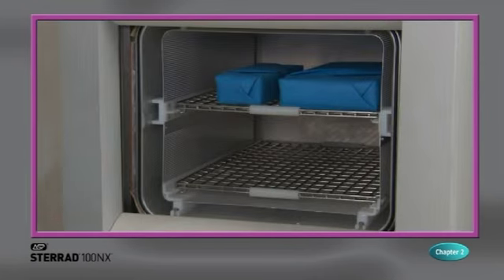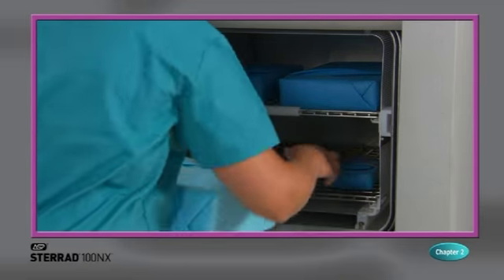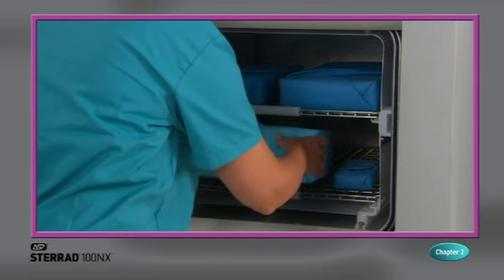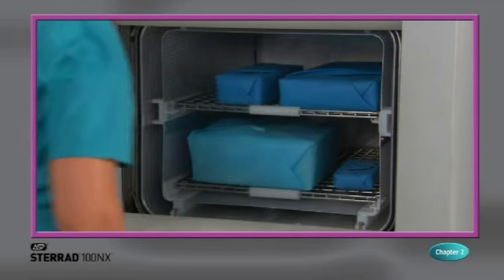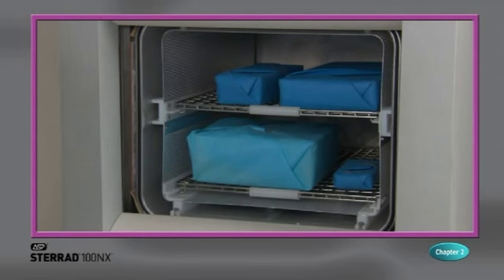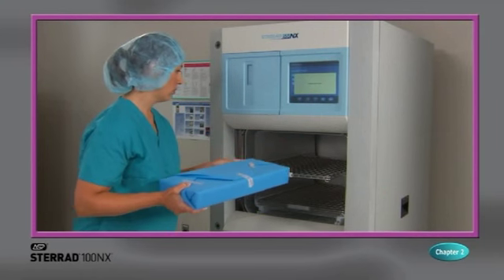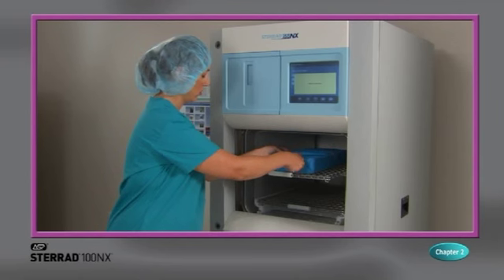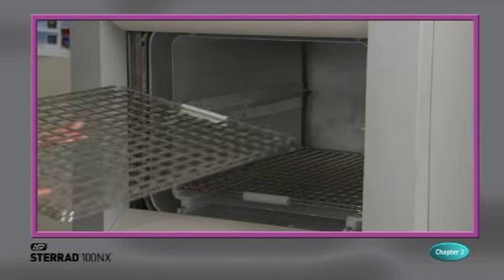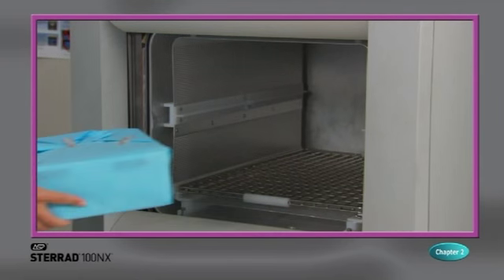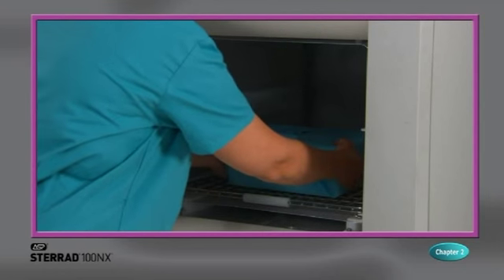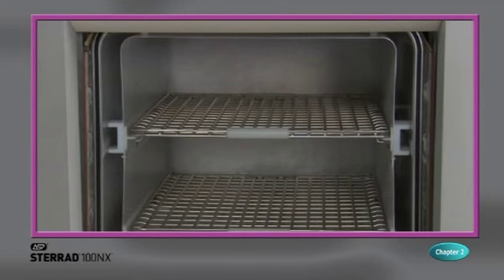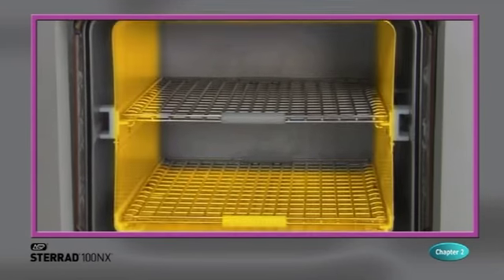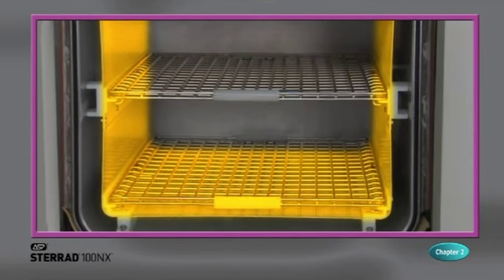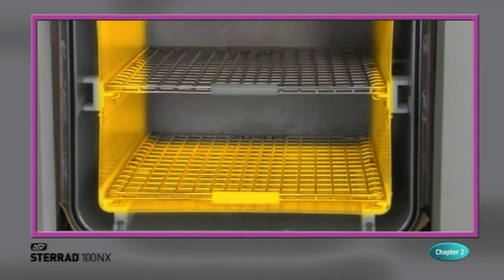The load is placed in the chamber for sterilization. The chamber walls and doors contain heaters that keep the chamber interior warm during operation. The chamber contains slide-out shelves to permit efficient loading. The top shelf is removable to facilitate larger trays. Inside the chamber, surrounding the shelves, is a metal screen, the electrode, that helps generate plasma during operation.